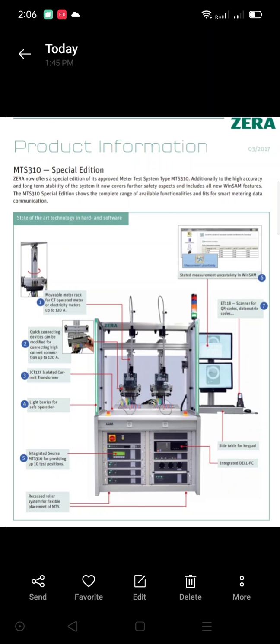We are doing the following tests by using all these Zera test benches based on IEC and IS standards specifications. For example, pre-warming test, accuracy test, starting current test, creep test, dial test, voltage and frequency unbalance, influence of harmonics, influence of voltage and frequency, etc. can be measured by using this test equipment. This is a general standard for basically all the energy meters.